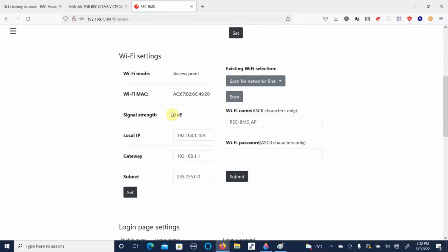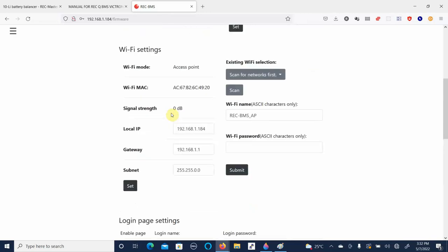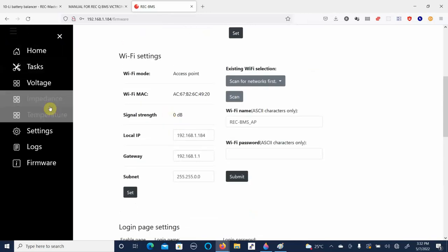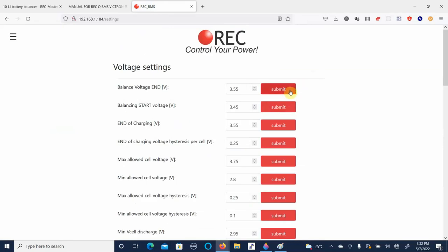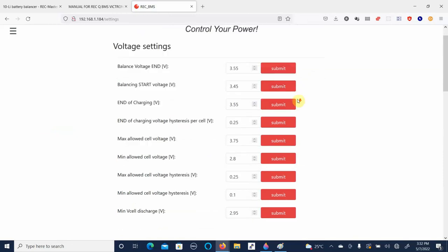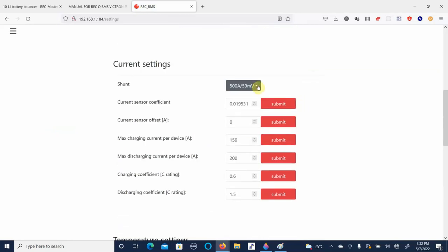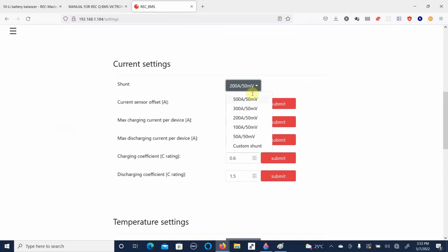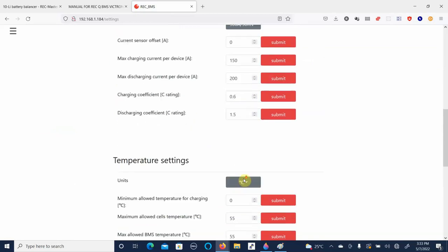I talked about the Wi-Fi settings in another module. But if we go back to our settings, we can see now we have a red submit button beside everything. For most systems, most people are using LFP batteries, we don't need to touch any of these variables. All we need to do is set our current shunt value here. The default is 500 amps. But if you're using a 200, you merely set it like that. We'll go back and we'll change it back to 500. Usually your current sensor offset will be set to 0. And then we have to set our maximum discharge current per device. But to get started, let's just leave all of these variables exactly where they are.